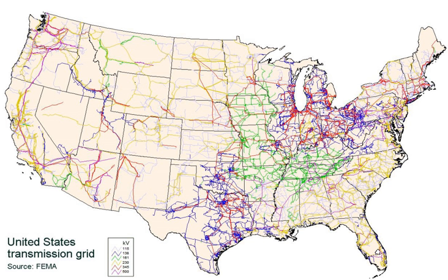For stable operation of the electrical grid of North America, power plants typically operate with a 4 or 5% speed droop. By definition, with 5% droop, the full load speed is 100% and the no load speed is 105%. Normally the changes in speed are minor due to inertia of the total rotating mass of all generators and motors running on the grid. Adjustments in power output for a particular prime mover and generator combination are made by slowly raising the droop curve by increasing the spring pressure on a centrifugal governor or by an engine control unit adjustment, or the analogous operation for an electronic speed governor.